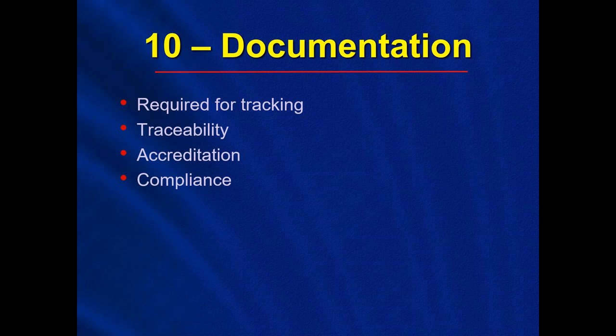And now it's come full circle where you want to be able to follow that scope from patient use to cleaning to decontamination to the next patient, and which scope was it, which accessories were used with it, and who it was used on. In the event that all of a sudden they get an issue with cross-contamination, you'll be able to determine exactly where that scope was at all times, who was responsible for cleaning. Again, traceability. You want that traceability, and you want to be auditing these things also. You want to audit the use of these scopes for documentation purposes. Joint Commission requires this for tracking, and you have to have this available.